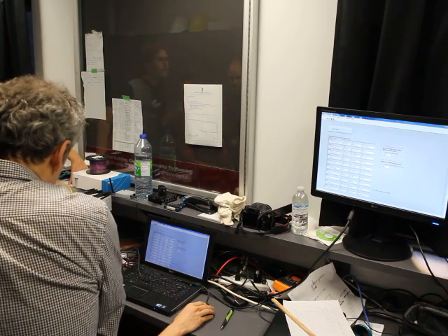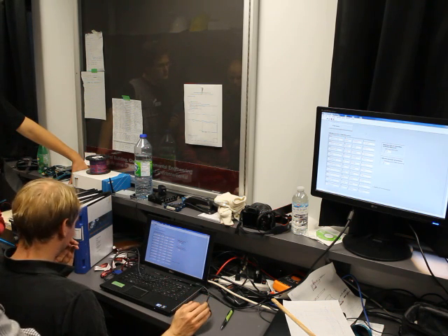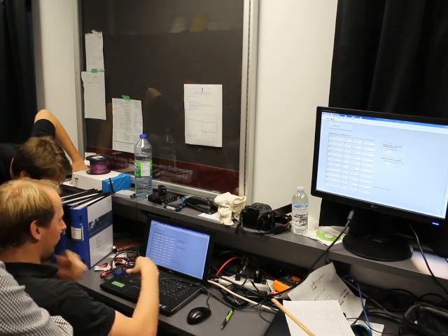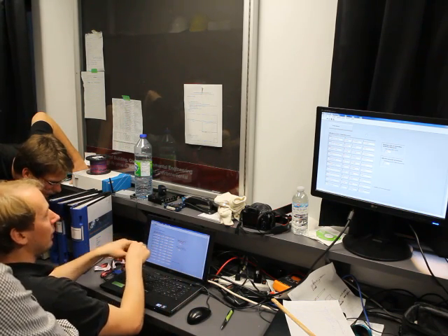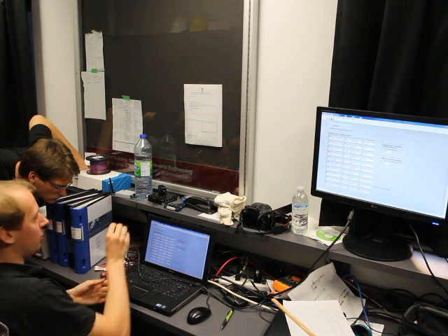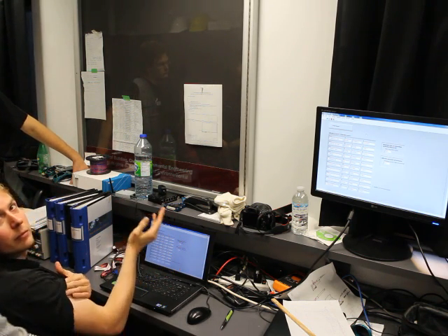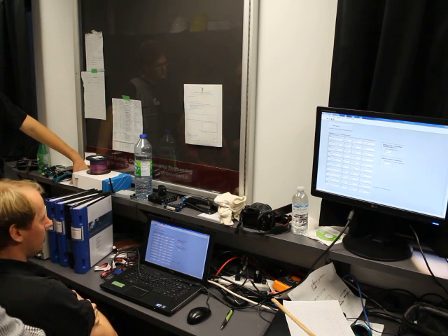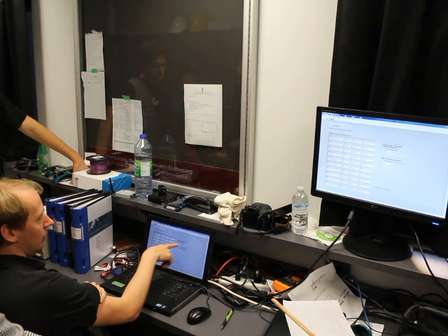So does the software do the calibration on its own, or do you have to do it separately and feed those numbers in? You have to do the calibration. You will get these values out of the calibration, put them in, and what we measure is just the resistance, and the software calculates the temperature from the resistance. Oh, I see. It's the relationship between the resistance and the temperature that you're determining in the calibration. Yes. And the same is true for the flow meter.